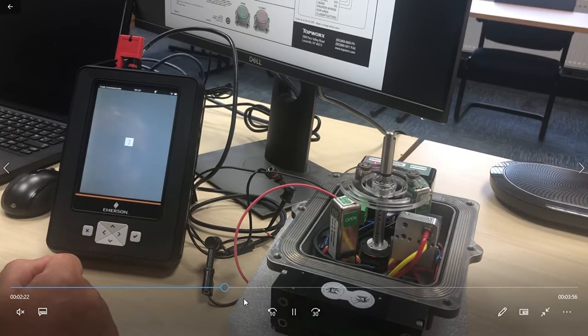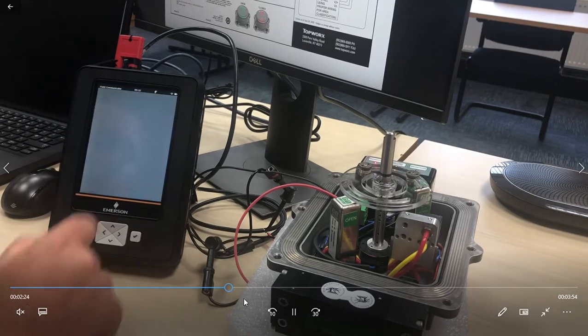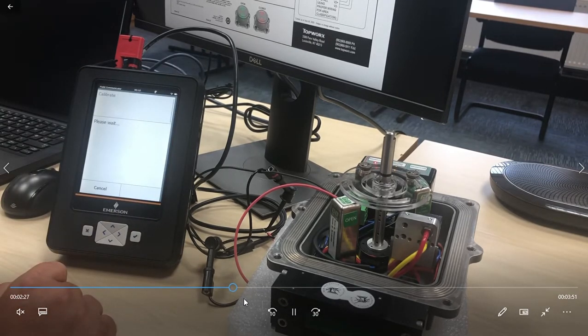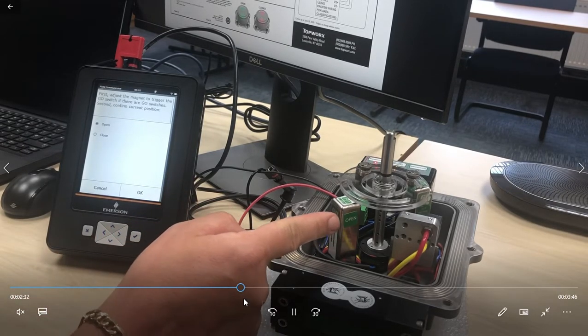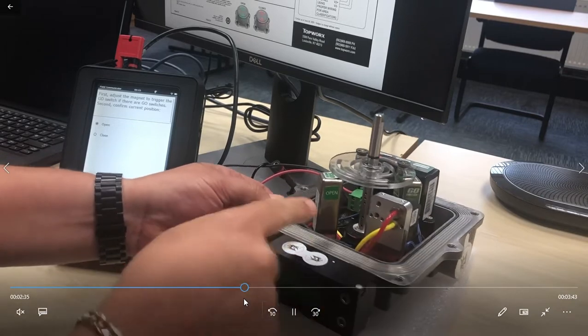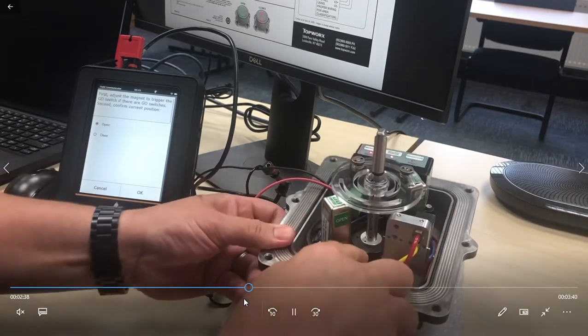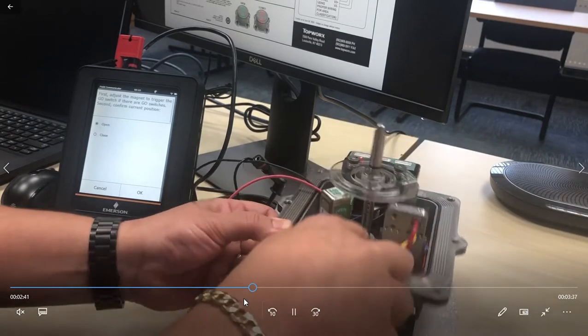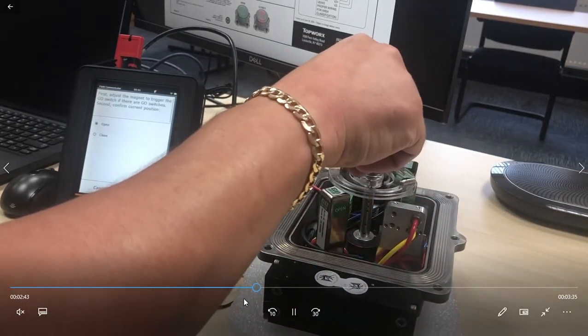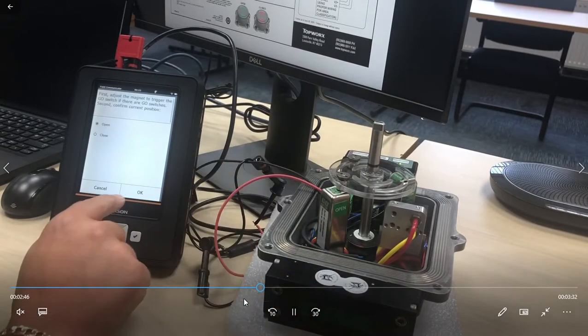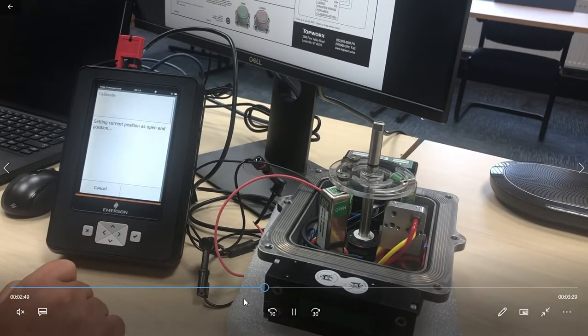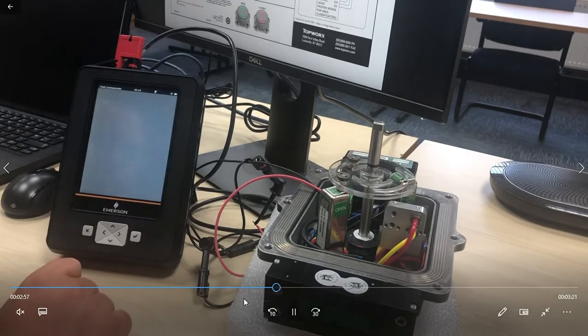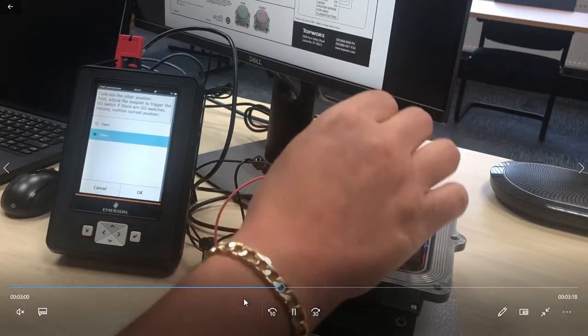A common feature when you're initializing or testing any of the Foundation Fieldbus devices is that calibration is needed, especially on a rotary device. So now what we have to ensure is with this particular device, we're going to go to the open position. There's a dead band on our transmitter, so we're just ensuring that it's the right way round. We can obviously move our devices to make that fit. So we're selecting the open position and we're ensuring it's not within the dead band. The dead band is indicated by two red dots, and that area is not able to be selected.